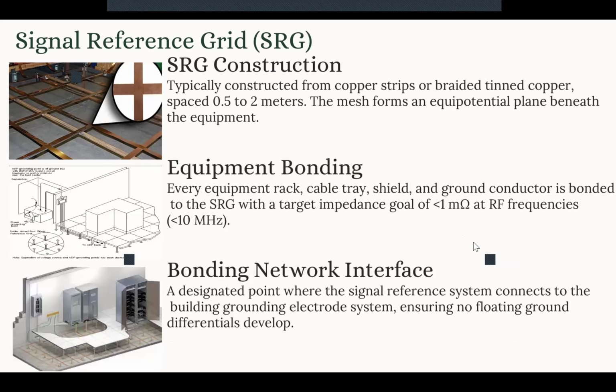maintain that quality. We mentioned the signal reference grid, the SRG, several times, and we said this is basically a network or mesh of interconnected conductors. You can see in the picture there are copper strips shaping a mesh underneath our facility, and the ground of every equipment should connect to that SRG. This is important. We already said there is a requirement that the space between these strips should be between 0.5 to 2 meters apart. These are the dimensions of these squares.